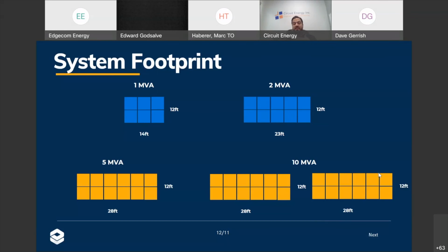And the nice thing about the technology that we use is that these can be double stacked. So in the case of a 5 megawatt or 5 MVA system, we will be looking at a 12 by 28 feet footprint, but then it'll be double stacked. So we'd have a total of 12 cabinets on the ground and 12 cabinets right above them. And in a 10 megawatt, the same thing. You'll have 2 platforms, each 12 by 28, double stacked onto one another to a maximum height of 20 feet.